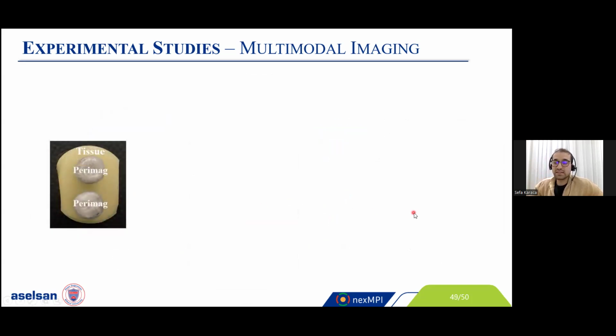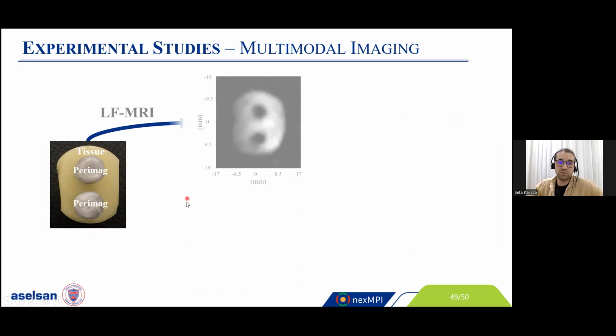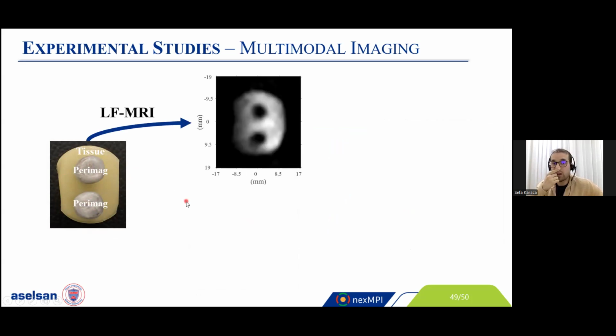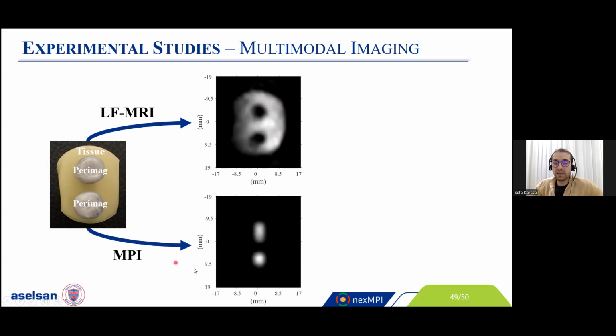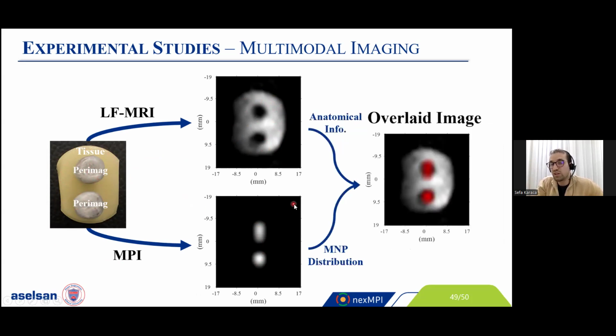This is the same story, but with a bit more complex phantom. In this case, we have two PCR tubes. If we perform low field MRI, you can see our results: we reconstruct the tissue part of our phantom. If we perform MPI, we can reconstruct the magnetic nanoparticle distribution of our phantom. At the end, in the overlaid image, we again have the advantage of both the anatomical part and the magnetic particle distribution.